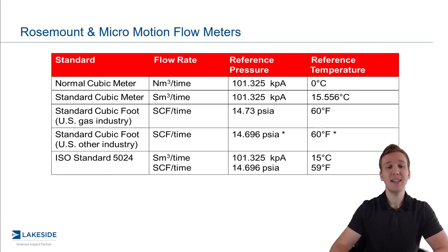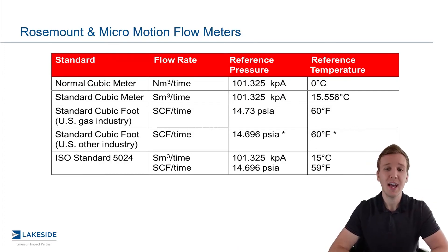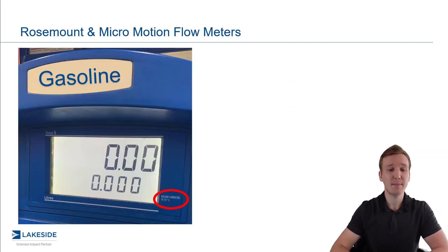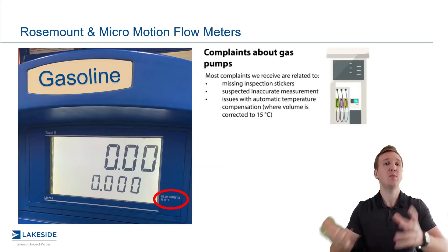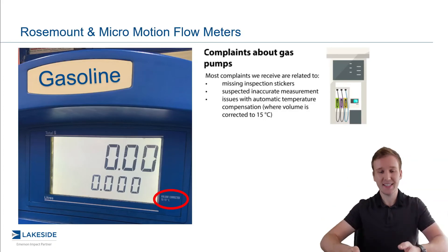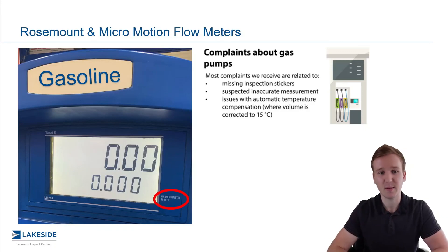There are different standards based on the industry you're in. We most commonly hear of normal cubic meters or standard cubic meters. As you can see in this reference table, the difference is what temperature we are referencing back to. If you go to fill up gas at the pumps, you're going to see volume corrected to 15 degrees Celsius. The reason we do this is to make sure we have a consistent set of conditions — so that when you buy gasoline you might not like the price, but at least it will be a consistent reference.